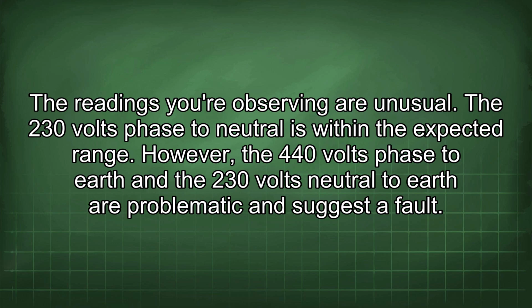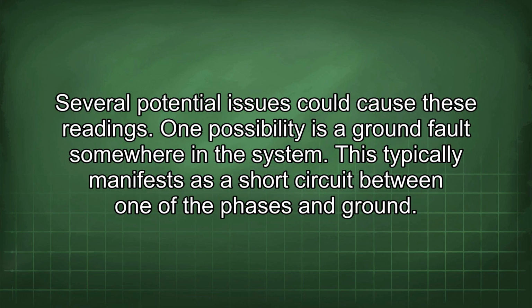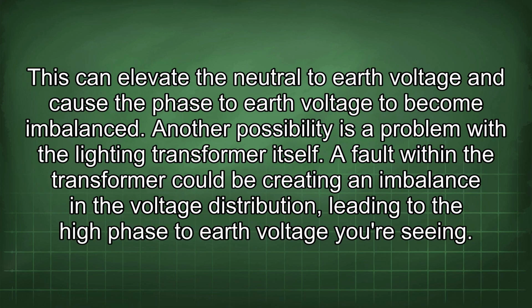The 230 volts phase-to-neutral is within the expected range. However, the 440 volts phase to earth and the 230 volts neutral to earth are problematic and suggest a fault. Several potential issues could cause these readings. One possibility is a ground fault somewhere in the system. This typically manifests as a short circuit between one of the phases and ground. This can elevate the neutral to earth voltage and cause the phase to earth voltage to become imbalanced.